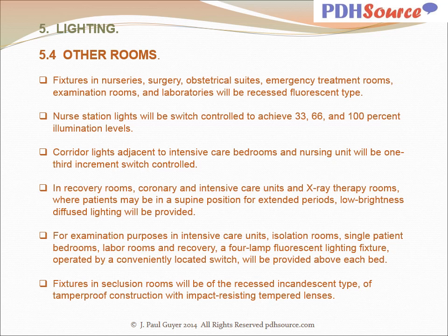Nurse station lights will be switch controlled to achieve 33, 66, and 100% illumination levels. Corridor lights adjacent to intensive care bedrooms and nursing unit will be 1/3 increment switch controlled. In recovery rooms, coronary and intensive care units, and X-ray therapy rooms where patients may be in a supine position for extended periods, low brightness diffused lighting will be provided.